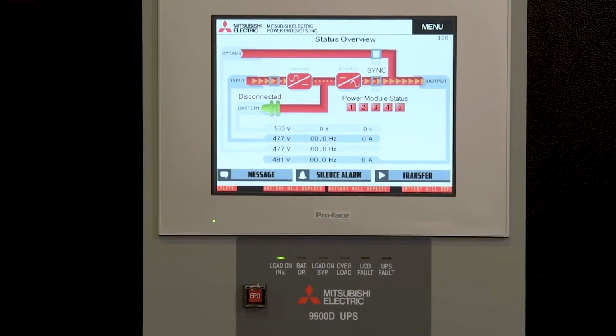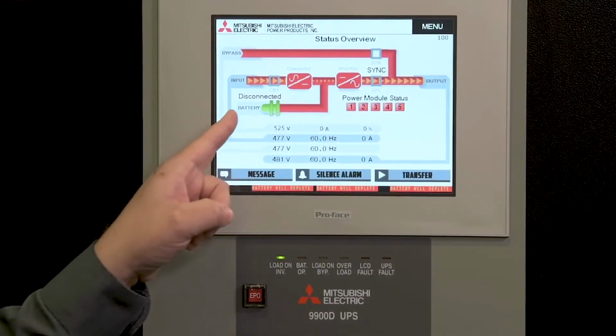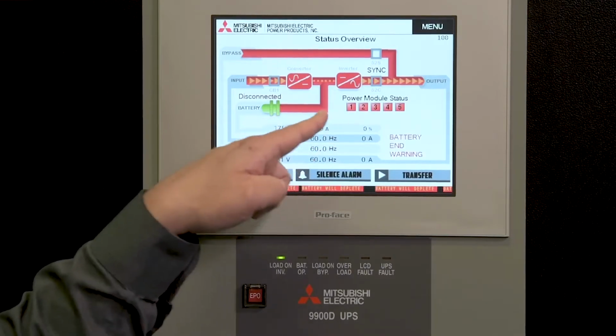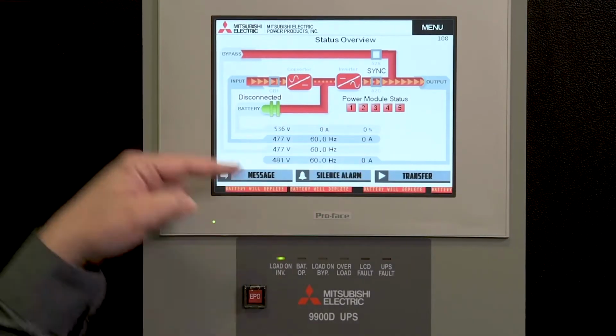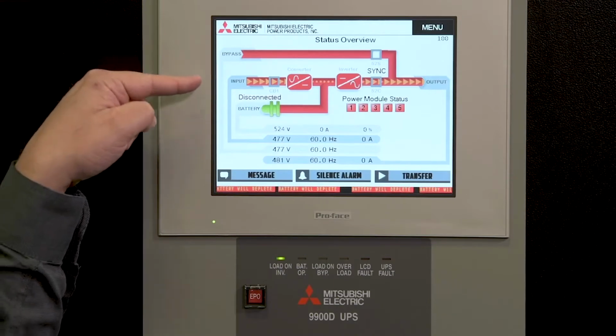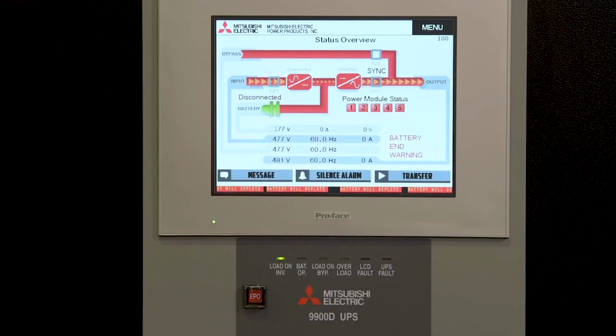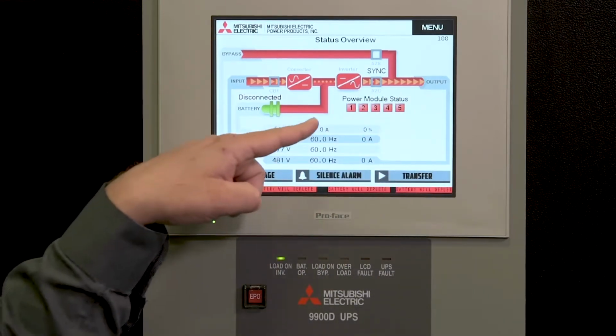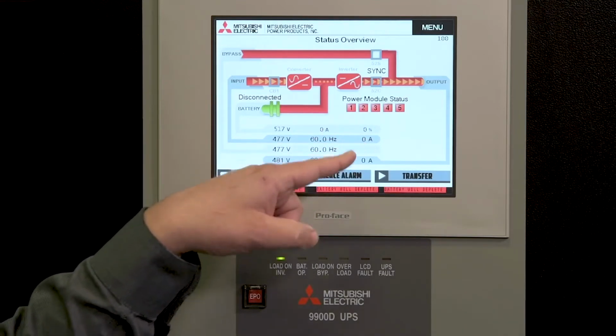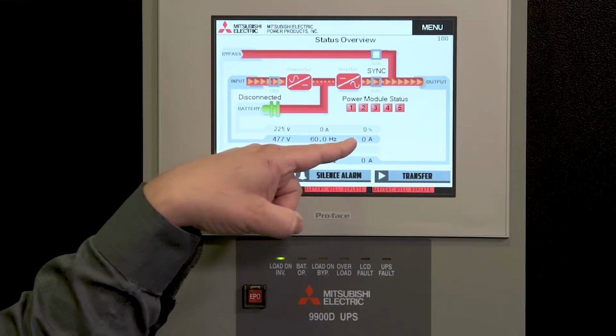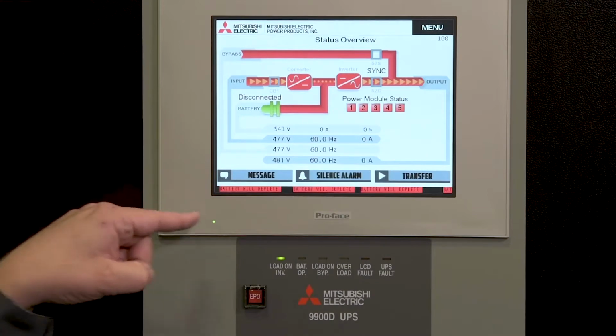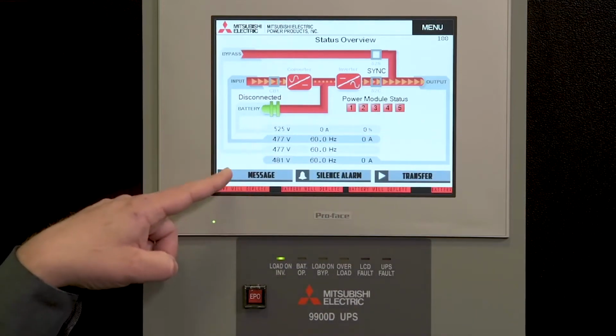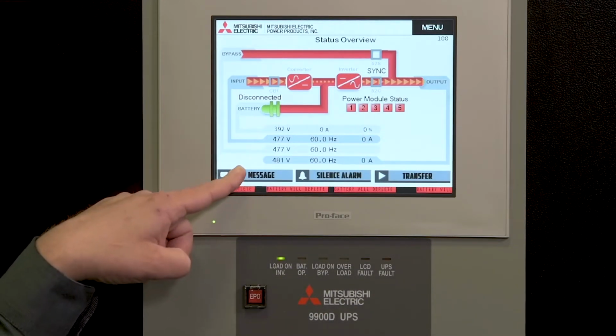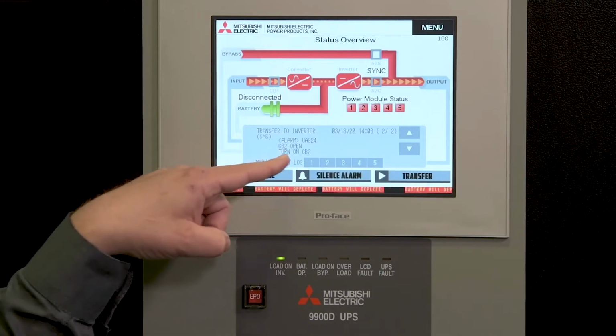So I wanted to take a second and show you the main screen while the batteries are disconnected, showing you that the batteries are isolated, all the 5 power module statuses are still on, and power is flowing from the input of the UPS through the UPS to the output source, and not in any power conditioning mode. In addition, we currently have alarms telling us that our battery disconnect is open, as well as that the UPS is alarmed because we have battery disconnected.